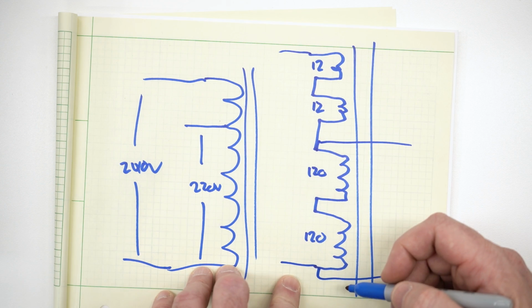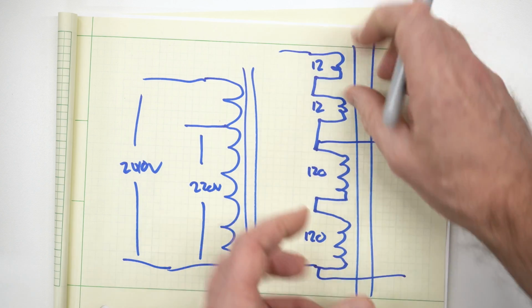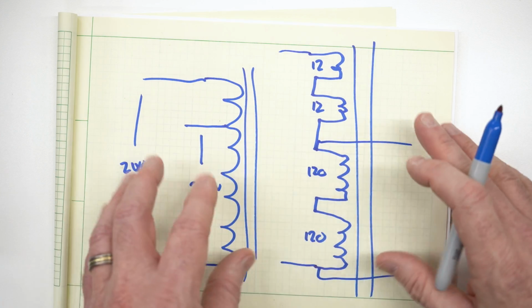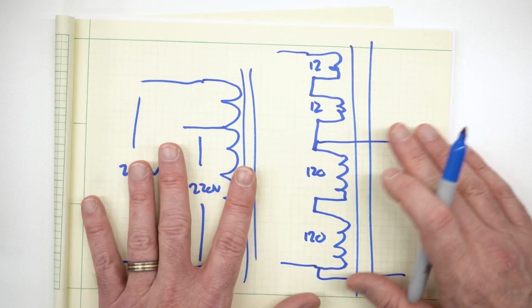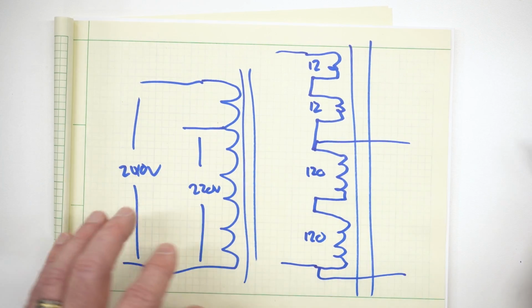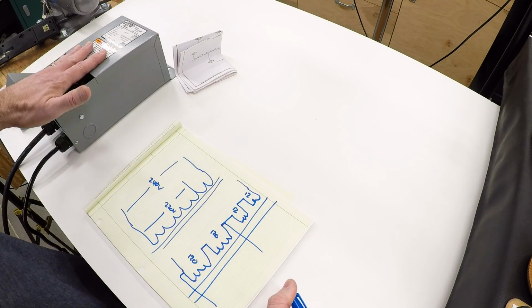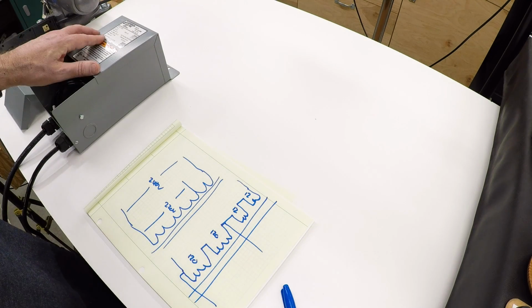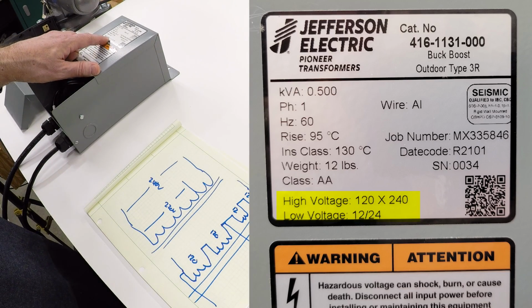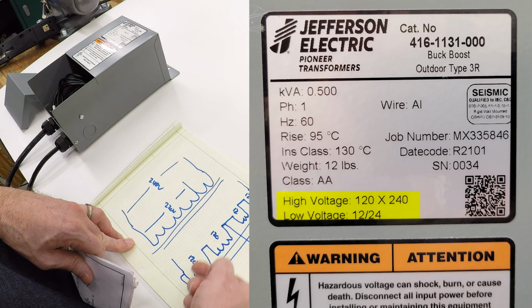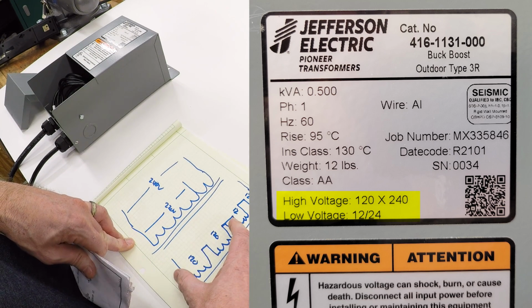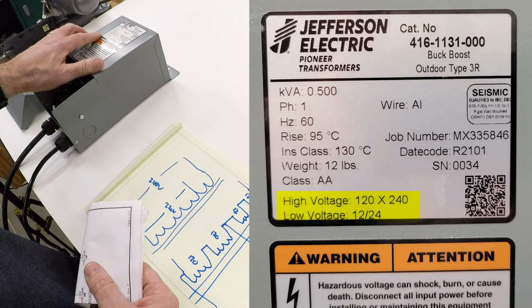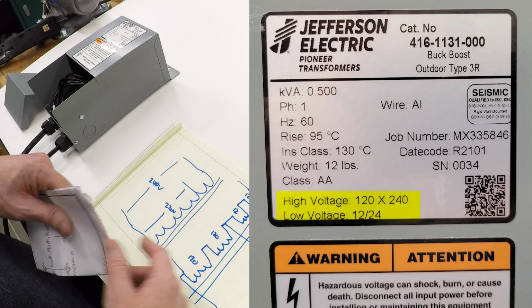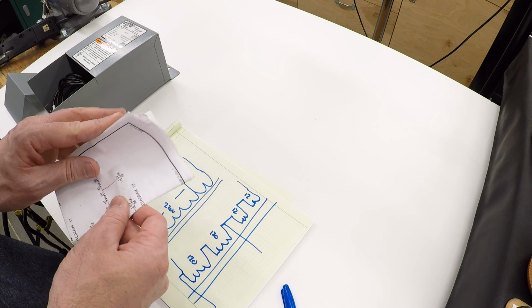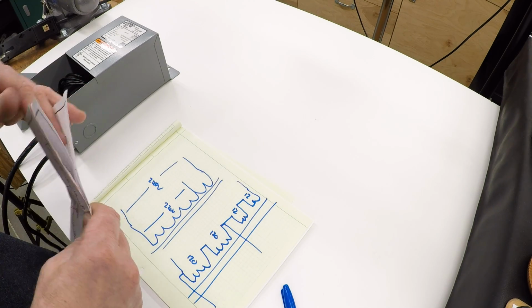Because you've got a bunch of different coils, you can run them in parallel or in series in different combinations to get different input and output voltages. That's exactly what's going on here. This is labeled high voltage 120 by 240 -- there are two 120s, which you can connect in parallel or in series. Low voltage says 12/24, because there are two 12-volt secondaries.